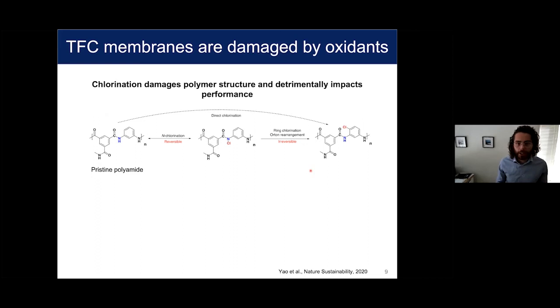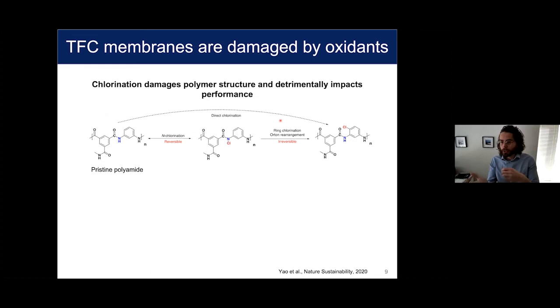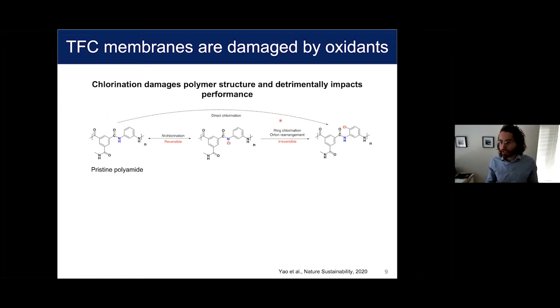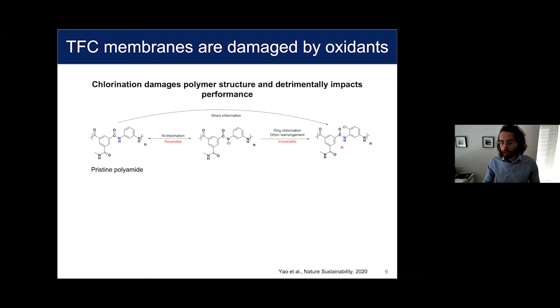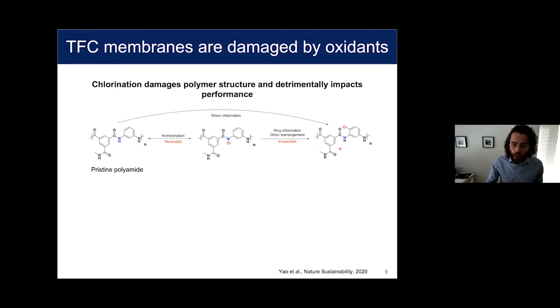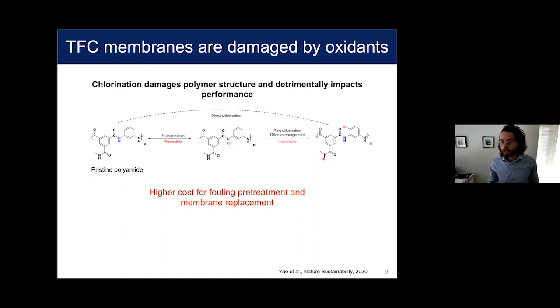The other issue with TFC membranes is that they're damaged by oxidants. If you're filtering water through a membrane for a long period, you'll get a buildup of organic matter and biological materials on the membrane that you want to clean off. Ideally you'd use something like chlorine or ozone, which are commonly used in water treatment. But with TFC membranes you can't do that — if you chlorinate them, you damage the structure of the polyamide and eventually degrade it. This just shows some reaction mechanisms of chlorination that damage the aromatic polyamide structure. What this means practically is you have to pretreat the water heavily before it reaches the membrane, or you need to think about replacing membranes after a shorter period, which adds cost.